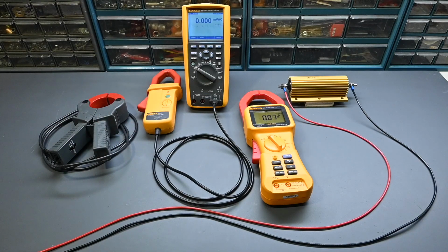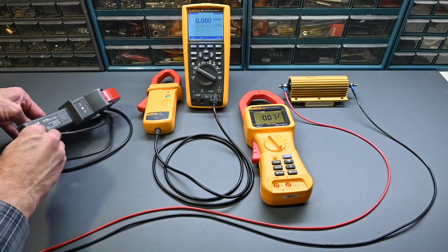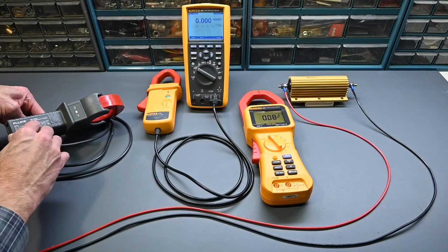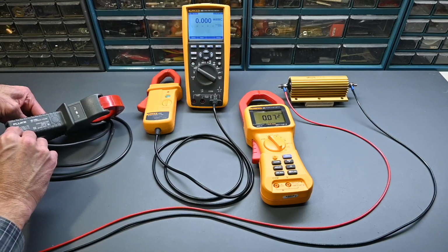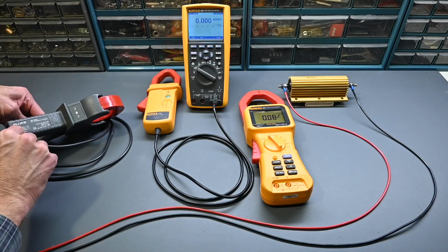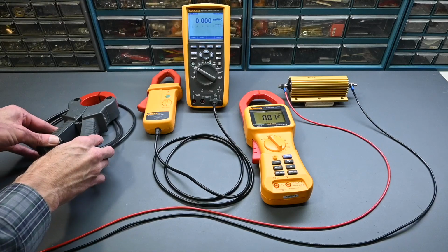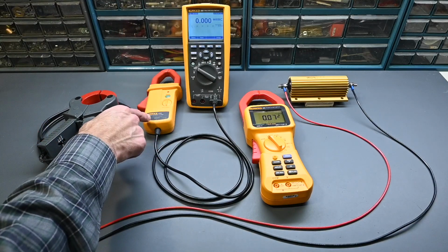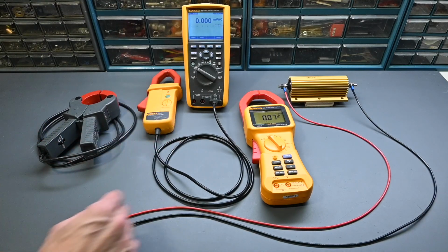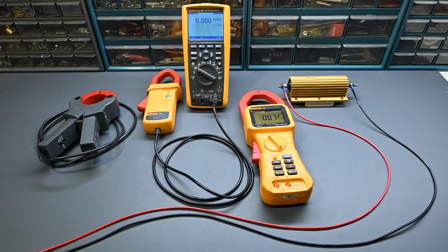Now most current clamps are not the best choice for extremely low currents unless the clamp is specifically made to sense in the low milliamps or perhaps microamp range, and such clamps do exist. But they're a very good choice for measuring extremely high currents, and clamps often measure hundreds or thousands of amps. So on this current clamp right here, the Fluke 80i 1000S, the current range goes from 100 milliamps up to 1000 amps, and it has 3 different ranges. There's a little range switch right here to select the range that you want. On this one, the Fluke i410, it goes up to 400 amps, and this Fluke 355 goes to 2000 amps.